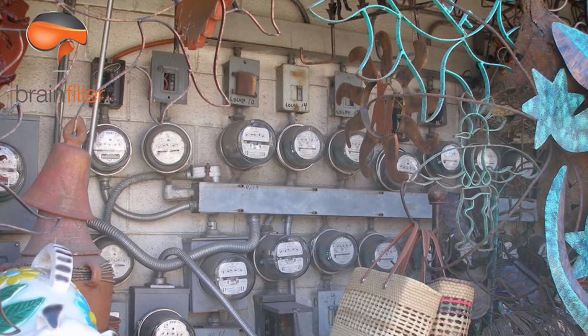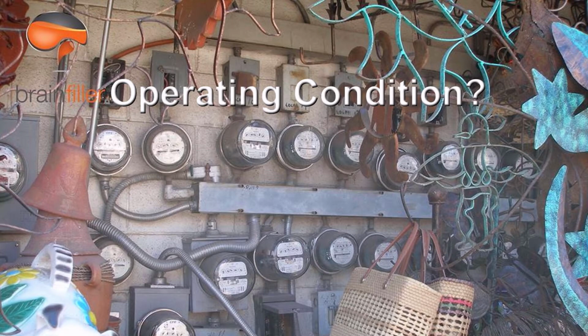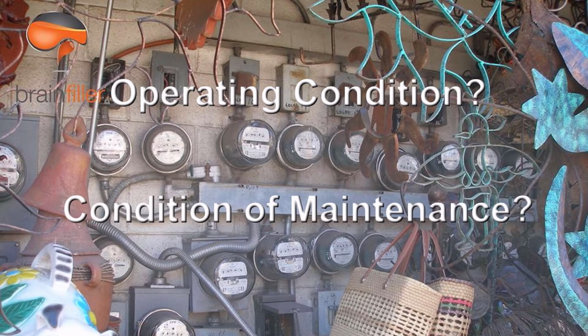But let's look at this. So we have item number 2, the condition of maintenance of the equipment. Well, okay. I actually took this photograph years ago, and if you were to try to make a judgment about the operating condition or a judgment about the condition of maintenance, I don't know. I don't think that would work out too well. So, you know, there's a lot that goes into this when you're trying to evaluate. Is there a shock hazard? Is there an arc flash hazard? For the shock hazard, if you look at this close enough, you'll see a few covers removed and things like that. I don't know if it's energized, but you don't know. I do have to give them credit for creative conduit routing. They made a very effective use of flex conduit for this one.